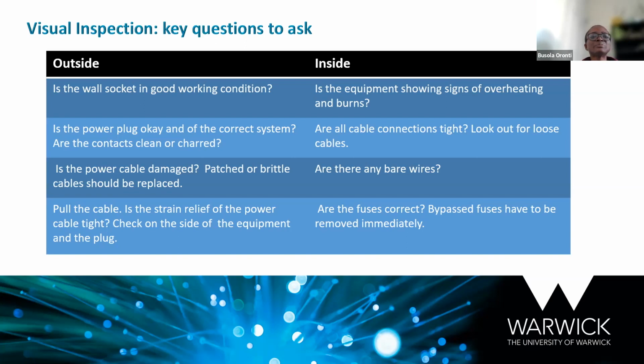Is the power cable damaged? Patched or brittle cables should be replaced immediately. Then pull the cables on the equipment side and on the plug side. Check the strain relief of the cable. Is it tight? So these are the things you can check outside of the equipment. Inside the equipment, you can look for signs of overheating and burns. And then you check whether all the cable connections are tight. Look for loose cables. Are there bare wires?